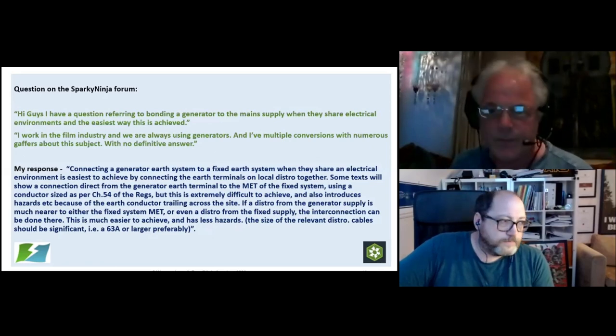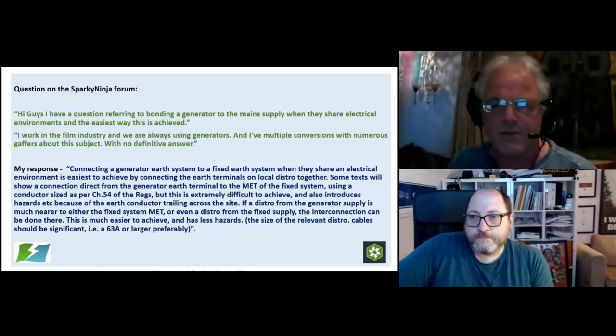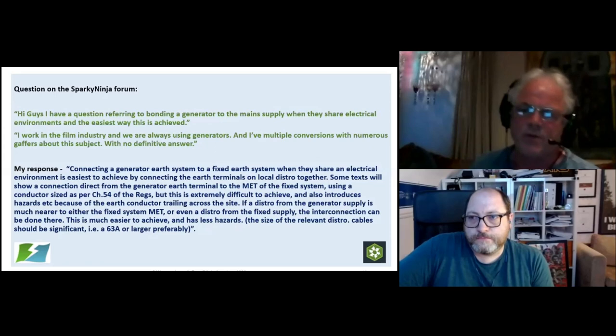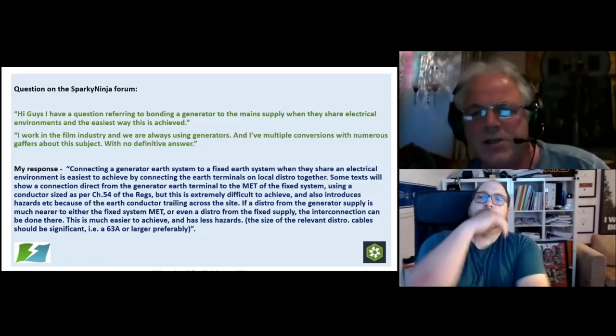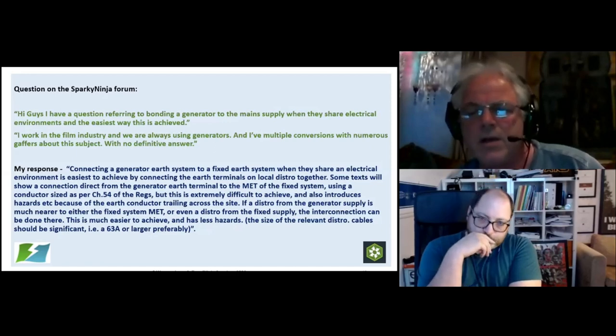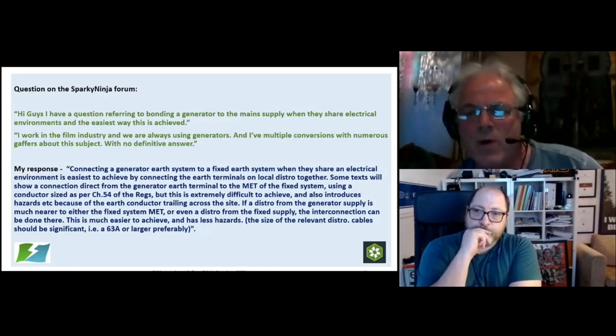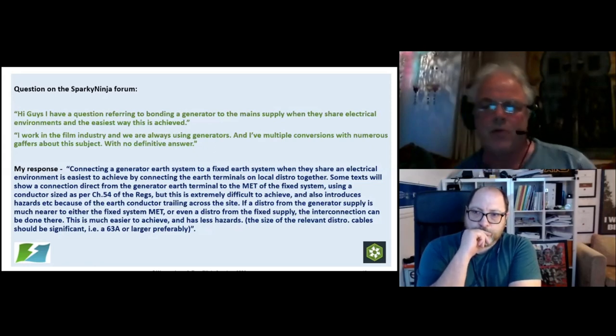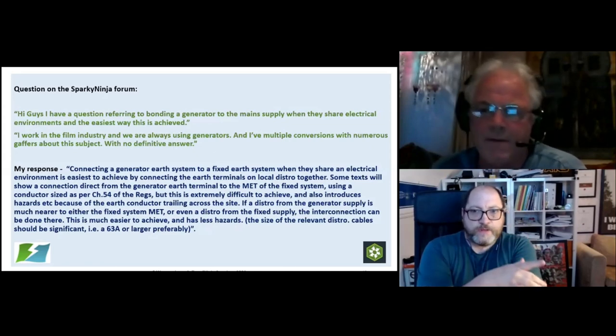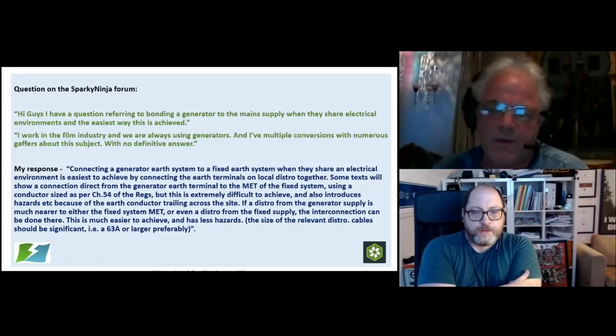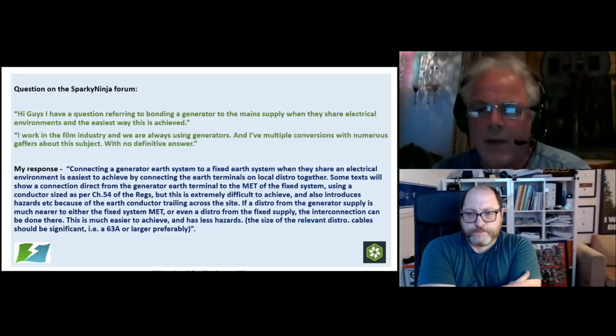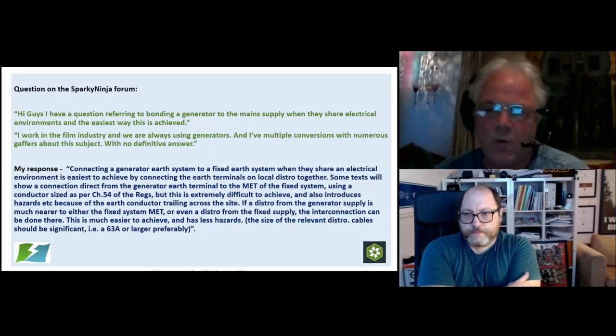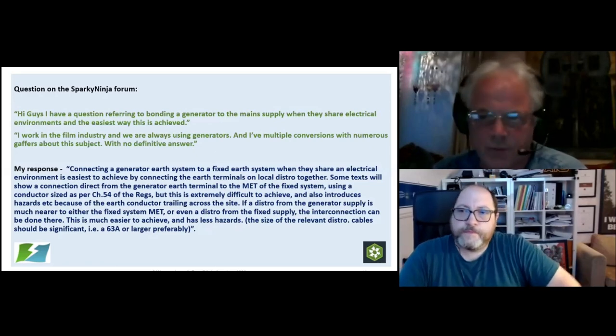Now what it actually says, or did state, was that you should take an earth conductor from the generator and connect it to the main earth terminal of the building. Now that earth conductor needs to be sized to chapter 54.7, yeah? So you can imagine it's going to be quite a chunky bit of cable. That's 7671. It could be 100 meters or more, or a couple of hundred meters across the floor, and then you're connecting onto the MET of the building. Well, the physical practicalities of that are quite difficult, and considering going into a distribution board or disconnecting an earth system, it's fraught with all sorts of problems.